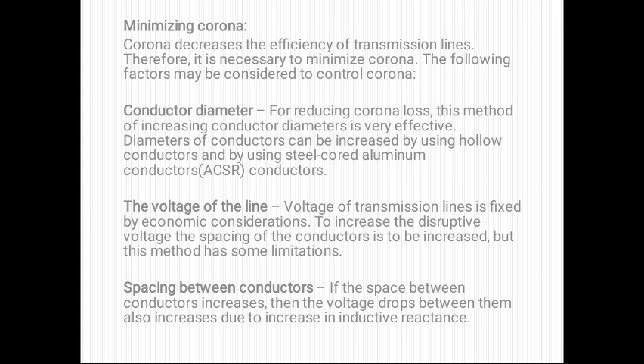Now there are some processes of minimizing the corona effect. Corona effect decreases the efficiency of the transmission line. Therefore, it is necessary to minimize corona. So the following factors may be considered to control corona loss. First is diameter of conductor. For reducing corona loss, this method of increasing conductor diameter is very effective. The diameter of the conductor can be increased by using hollow conductors and by using steel cored aluminum conductors, ACSR conductors.